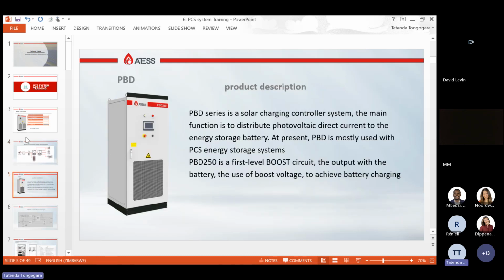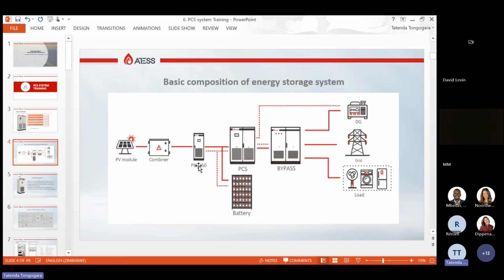So I'll start with this PBD 250. PBD, this is our MPPT. So it's a 250 kilowatt MPPT with 5 modules inside. So each module is 50 kilowatt. Now on this one, you can have different orientations. So each MPPT module should be connected to the same orientation. So there are 5 inputs, 5 PV inputs inside the PBD.